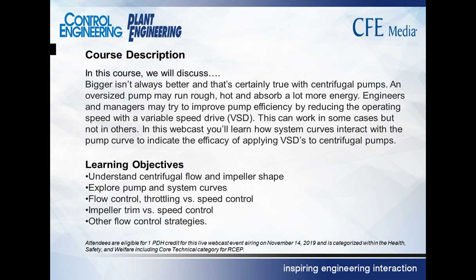Bigger isn't always better, and that's certainly true with centrifugal pumps. An oversized pump may run rough, hot, and absorb a lot more energy. Engineers and managers may try to improve pump efficiency by reducing the operating speed with a variable speed drive, or VSD. This can work in some cases, but not in others. In this webinar, you'll learn how system curves interact with the pump curve to indicate the efficacy of applying VSDs to centrifugal pumps. A certificate of completion will be available for each participant to download upon successful completion of a test at the end of the presentation.